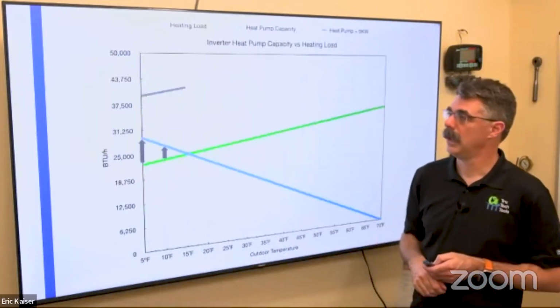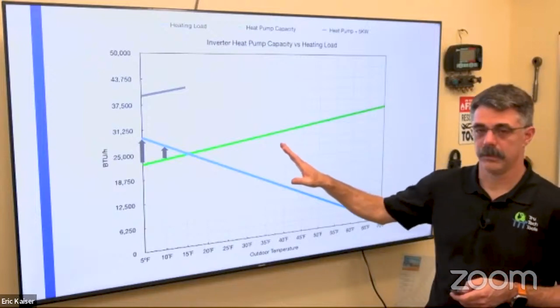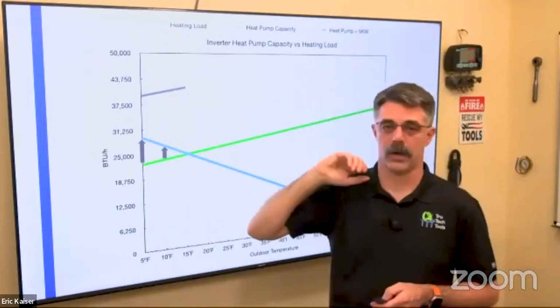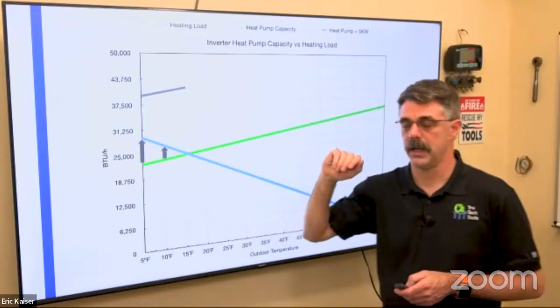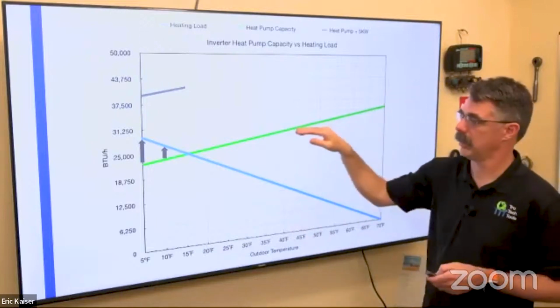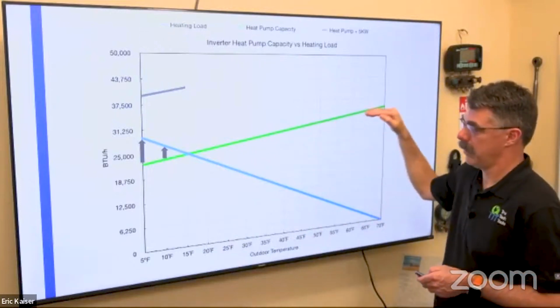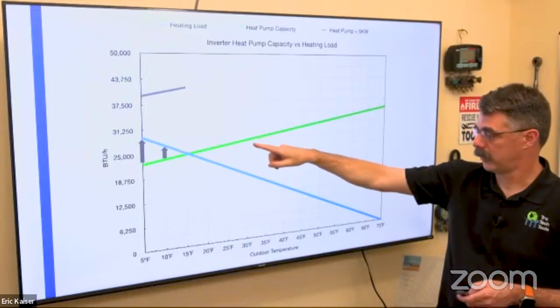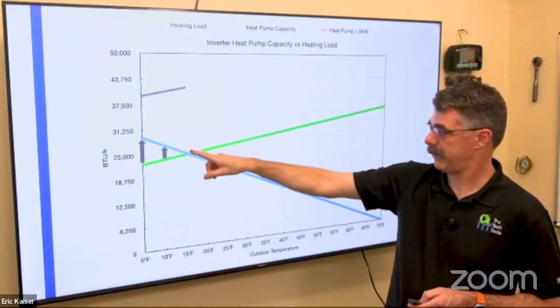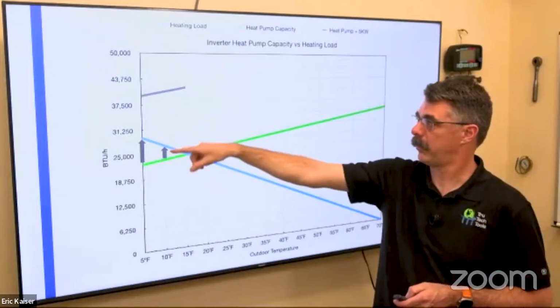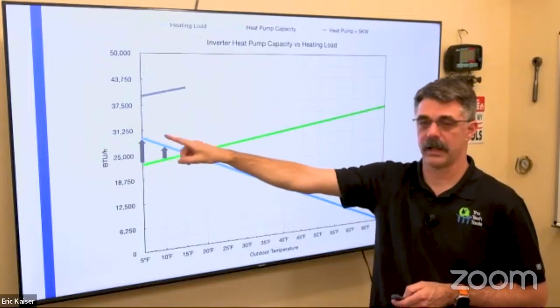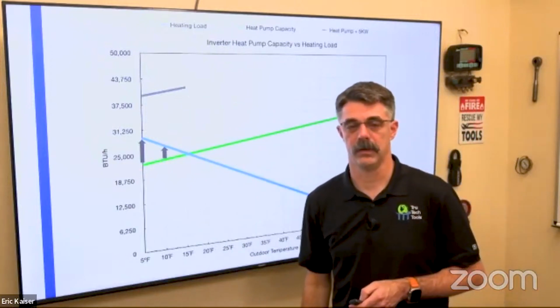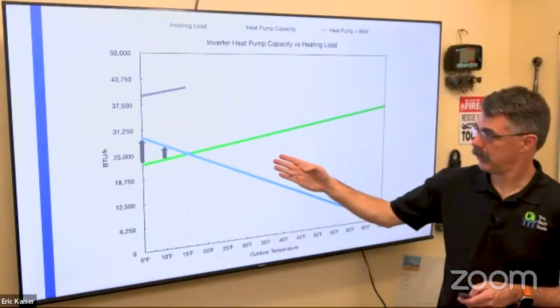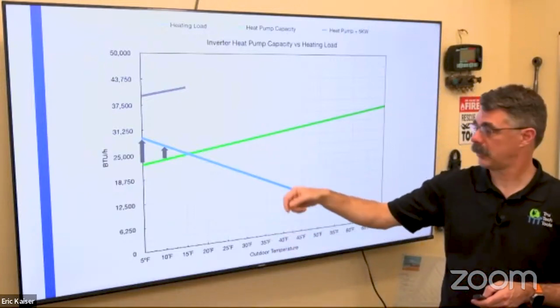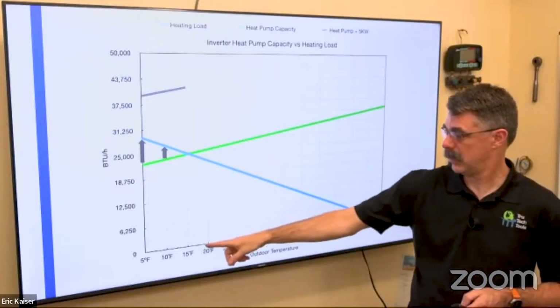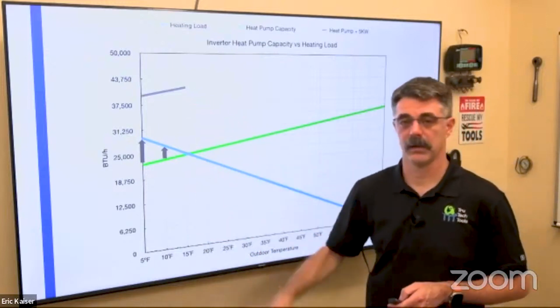All right. So a little different. This is with that inverter we talked about earlier, right? It's the air capacity controlled. Remember, it had a flatter slope. So I could take that down to say 15 degrees on this house before I've got to bring on a little and start cycling my electric heat off and on. So just shy of 30, about 29 for the single stage, or maybe 16 on my calculation for this one.